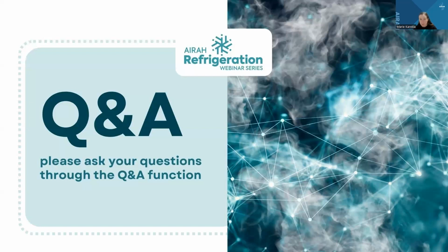Yeah. Yep, great, thank you. Next question here is, what would be some points to consider for cold or dry stores for archive stores? I think the thing is what sort of humidity is required in an archive store, right? Obviously, the humidity required determines the design of the evaporator coil.